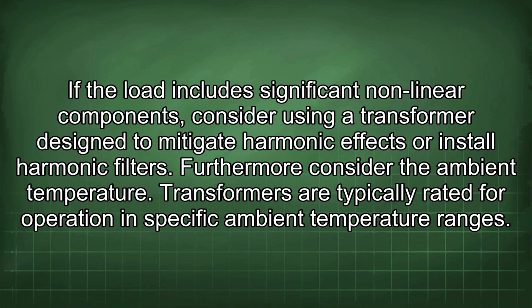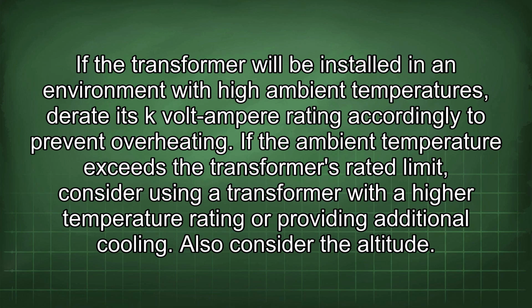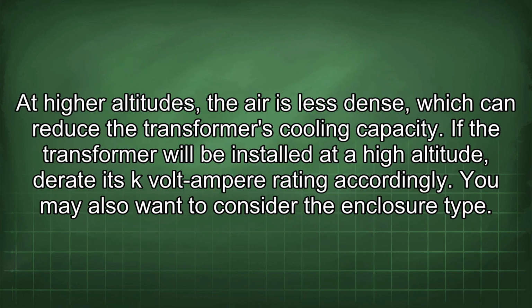Furthermore, consider the ambient temperature. Transformers are typically rated for operation in specific ambient temperature ranges. If the transformer will be installed in an environment with high ambient temperatures, derate its kVA rating accordingly to prevent overheating. If the ambient temperature exceeds the transformer's rated limit, consider using a transformer with a higher temperature rating or providing additional cooling. Also consider the altitude. At higher altitudes, the air is less dense, which can reduce the transformer's cooling capacity. If the transformer will be installed at a high altitude, derate its kVA rating accordingly.